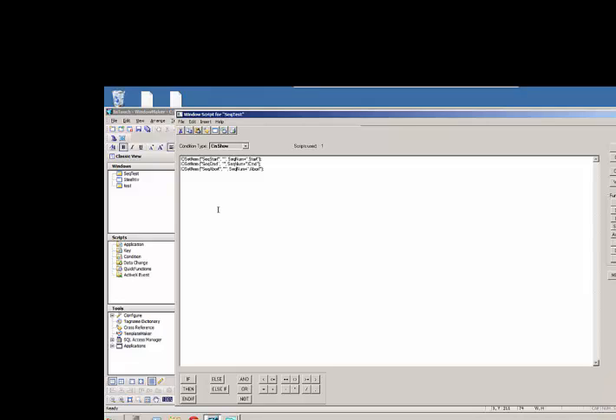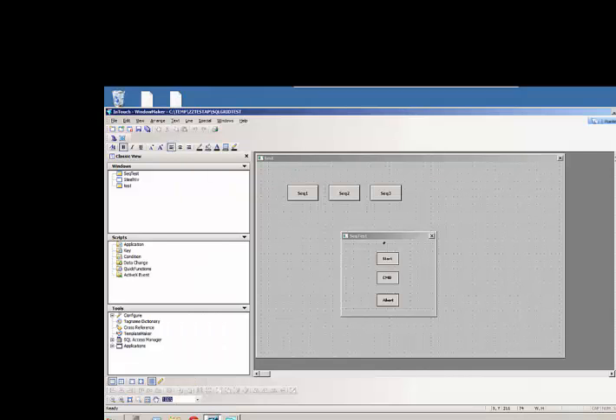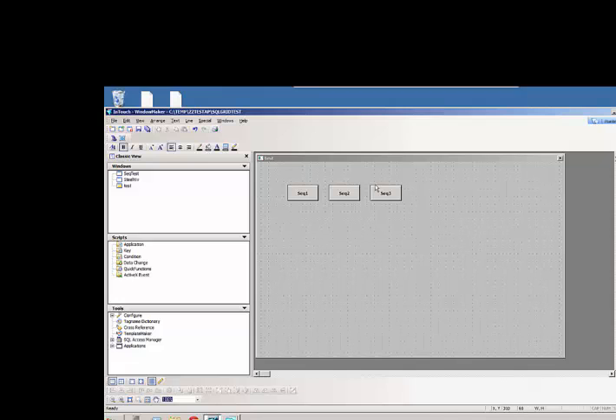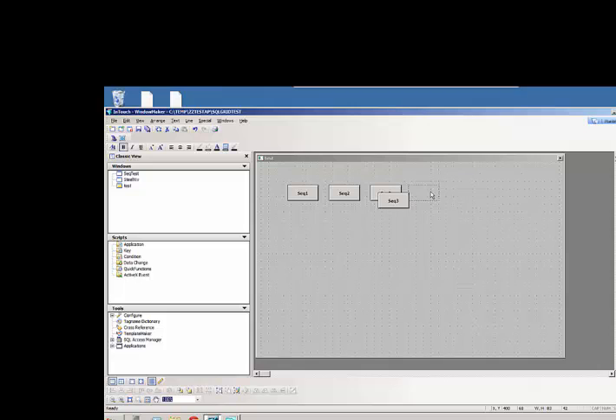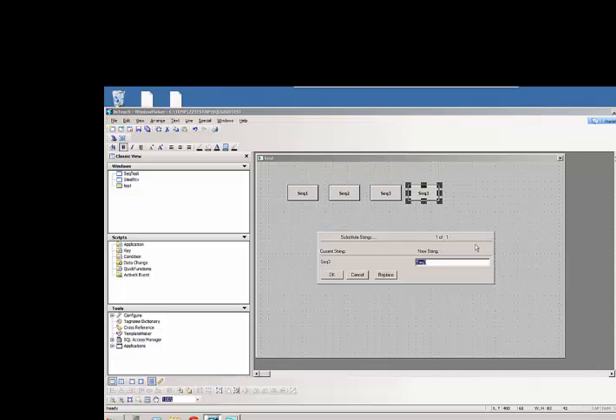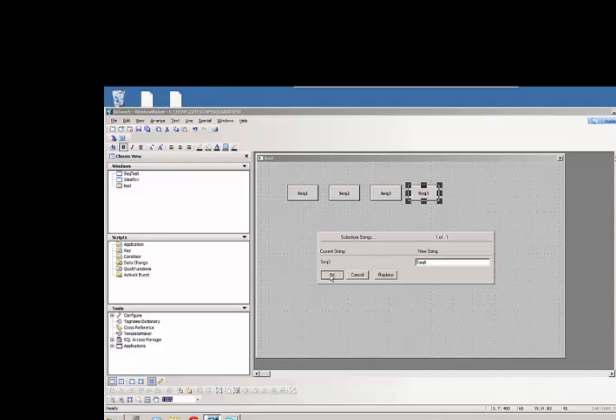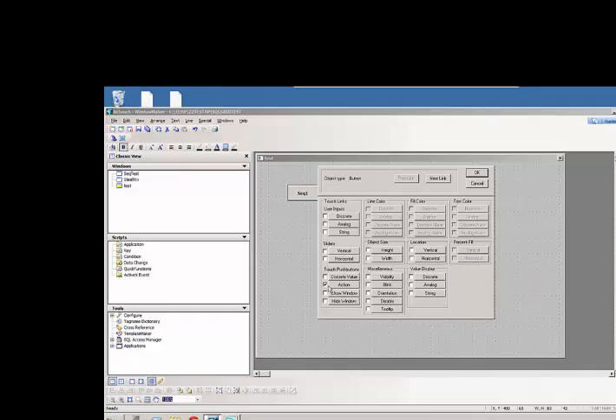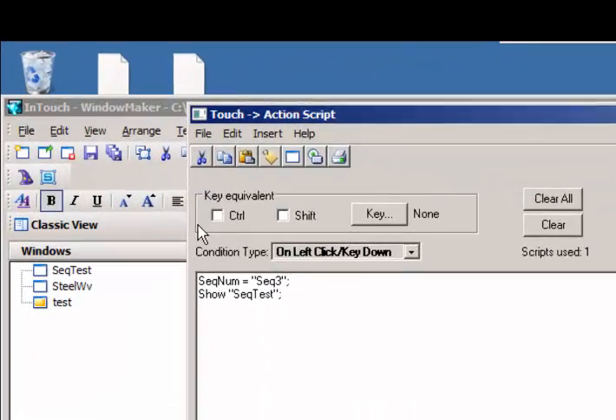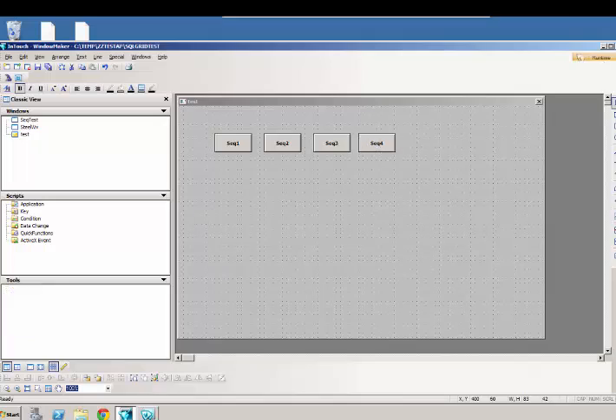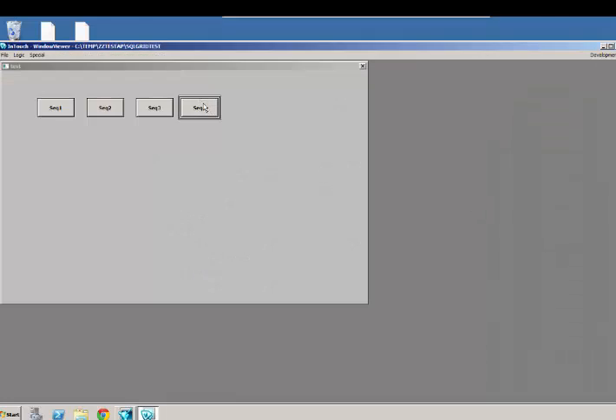This way, the user can actually create one faceplate, reuse that faceplate over again. All he needs to do if I want to create a next sequence number, I go here and duplicate this, point this up here, make this substitute my strings, make this sequence number 4, just from an aesthetic perspective, and then I go here and I change this to point to sequence number 3, and if I have sequence number 4, and then if I have a user-defined data type of sequence number 4 in my PLC, that's all I need to do.